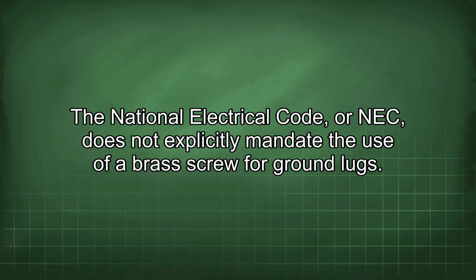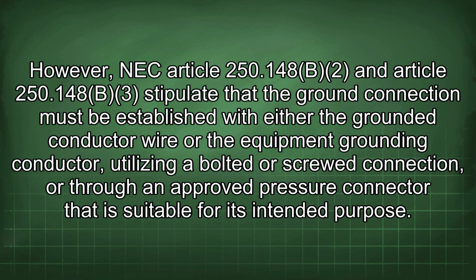The National Electrical Code, or NEC, does not explicitly mandate the use of a brass screw for ground lugs. However, NEC Article 250.148(B)(2) and Article 250.148(B)(3) stipulate that the ground connection must be established with either the grounded conductor wire or the equipment grounding conductor, utilizing a bolted or screwed connection, or through an approved pressure connector that is suitable for its intended purpose.